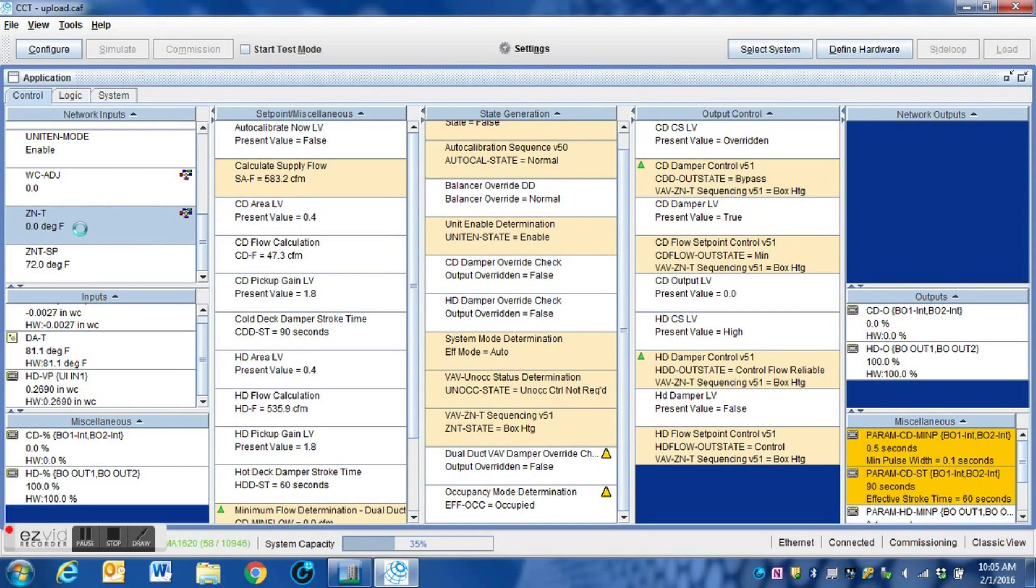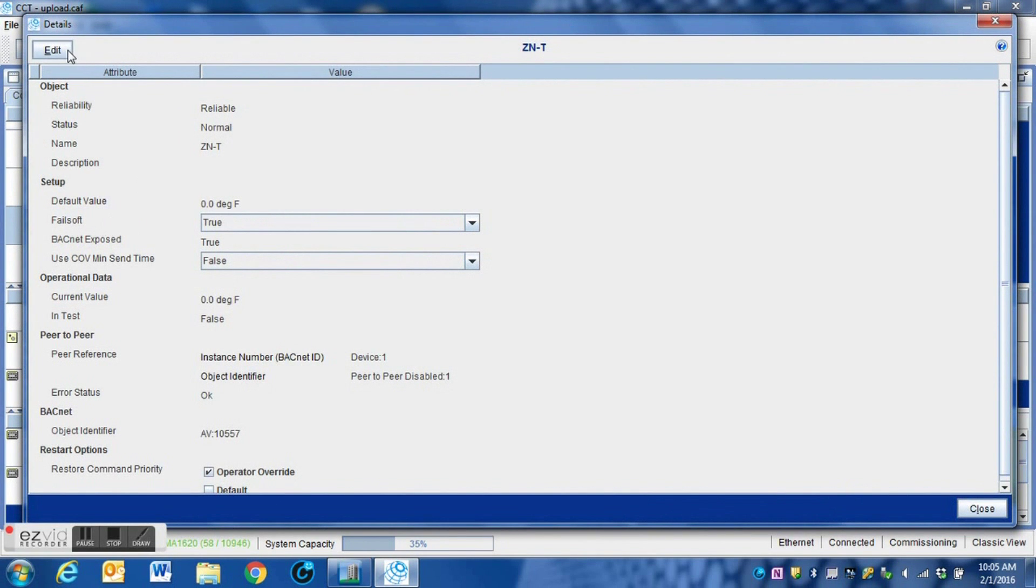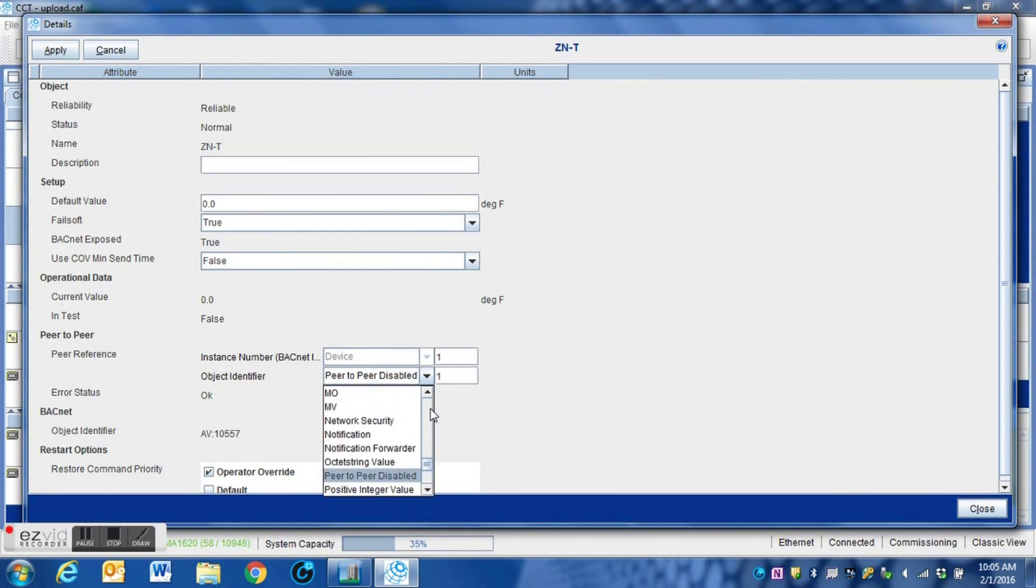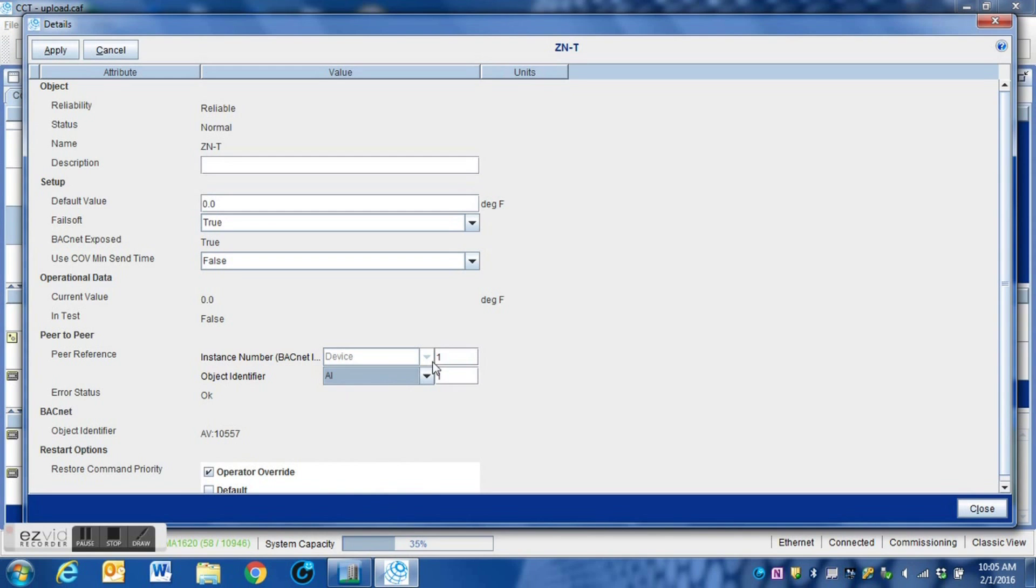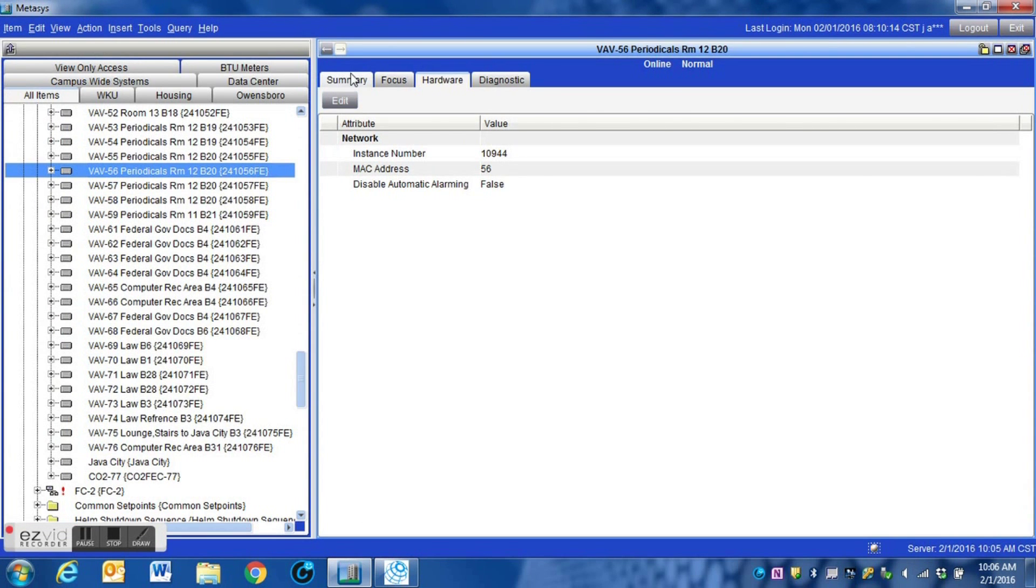So we open our program in CCT and commission into the program here of the device we're going to be sending the information to. I click my edit button here. I'm going to go from this drop-down window here. I'm going to select AI, and in this box I'm going to enter that instance number of that particular controller, our source controller.